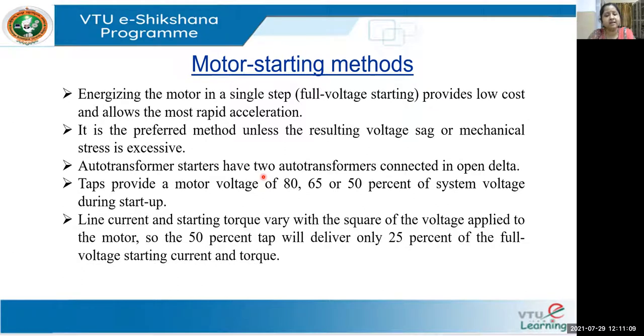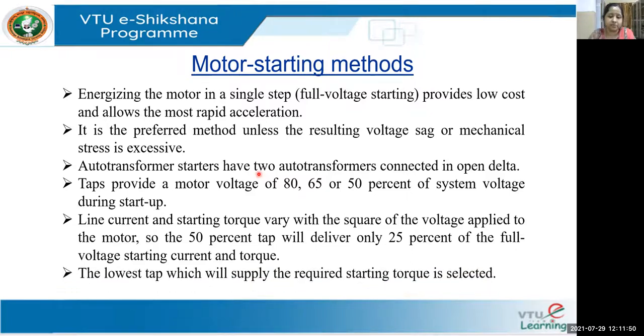Since line current and starting torque both increase with the square of the voltage, a 50% tap will deliver only 25% of the full-voltage starting current and torque. The lowest tap which will supply the required starting torque is selected. For a given starting voltage, resistance and reactance starters draw more current from the line than autotransformer starters, but this type of starter provides higher torque. Reactors are typically provided with 50%, 45%, and 37.5% tappings to control inrush current at the beginning.